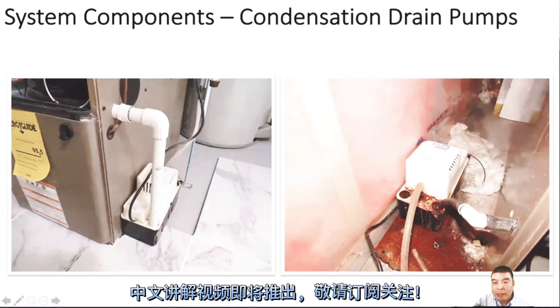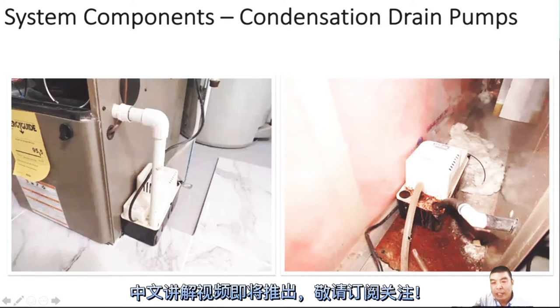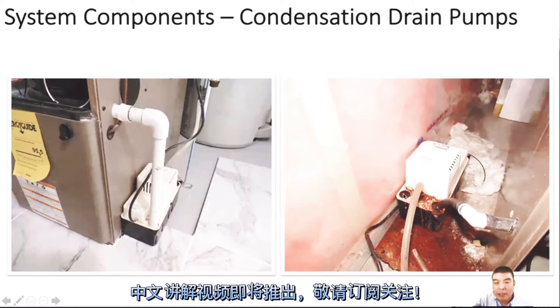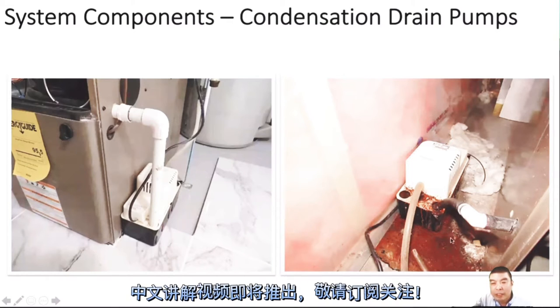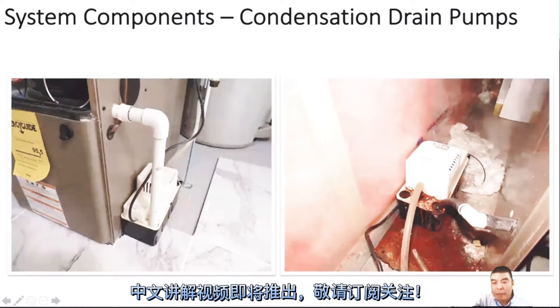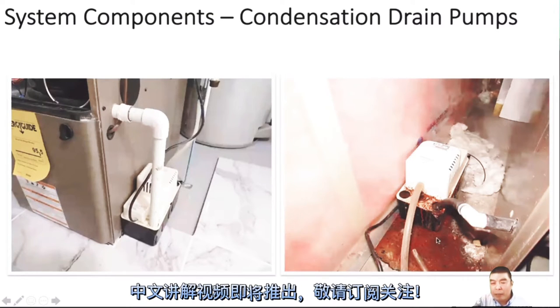On the right side here there is a water leak. Maybe this pump is blocked and cannot pump the condensate water out, or maybe something inside the pump is broken and not running. The water is right from here, just around the pump, and there are lots of stains here. So maybe we need to change this condensate pump. Anything about water in the house is a big trouble — big damage. Everywhere there's a water pipe, we should be careful.